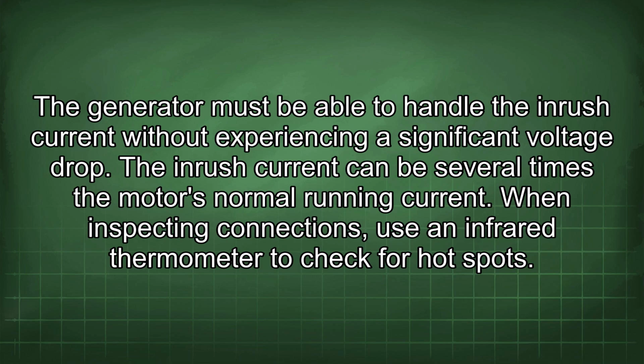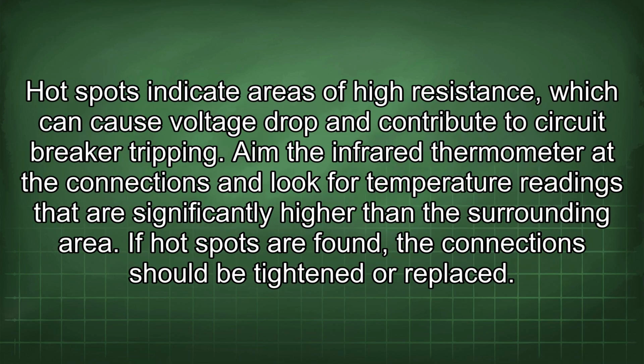When inspecting connections, use an infrared thermometer to check for hot spots. Hot spots indicate areas of high resistance, which can cause voltage drop and contribute to circuit breaker tripping. Aim the infrared thermometer at the connections and look for temperature readings that are significantly higher than the surrounding area. If hot spots are found, the connection should be tightened or replaced.